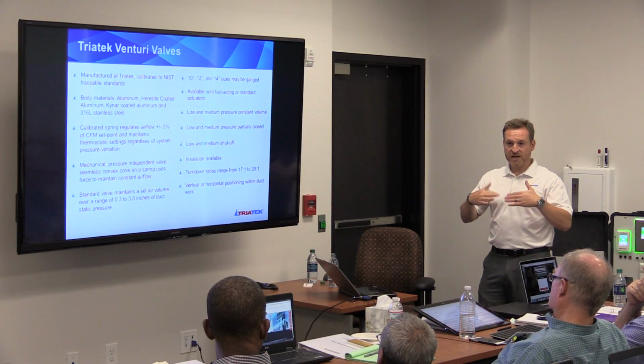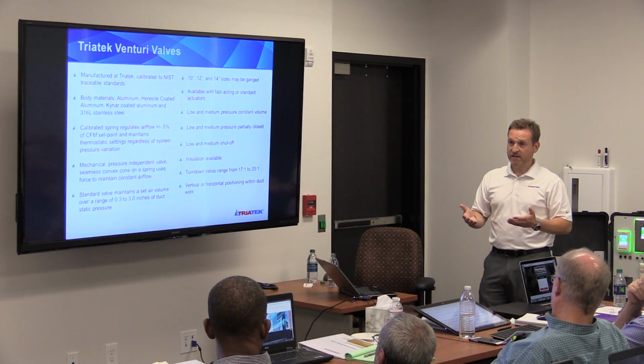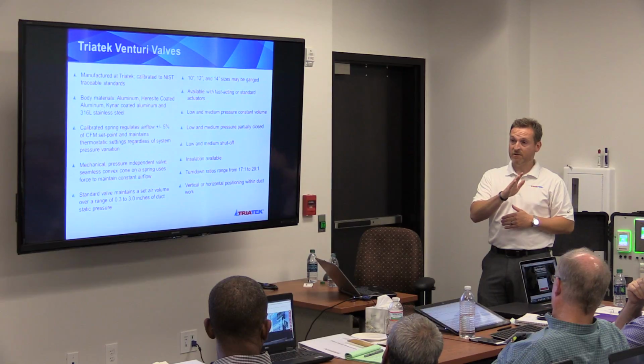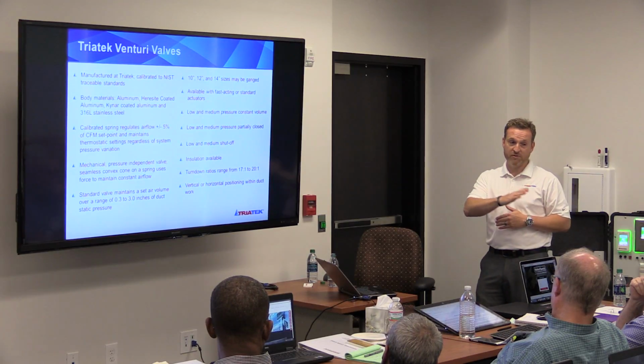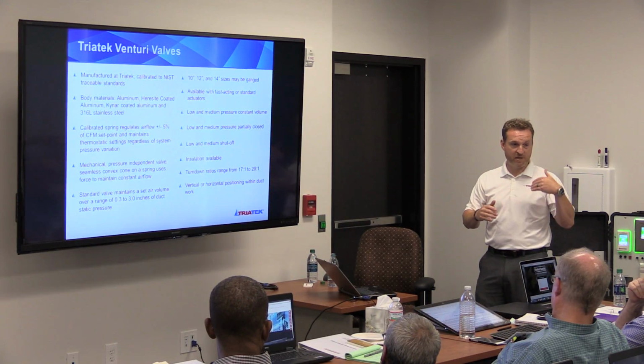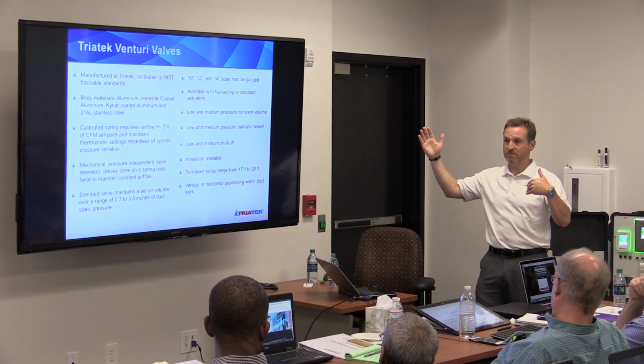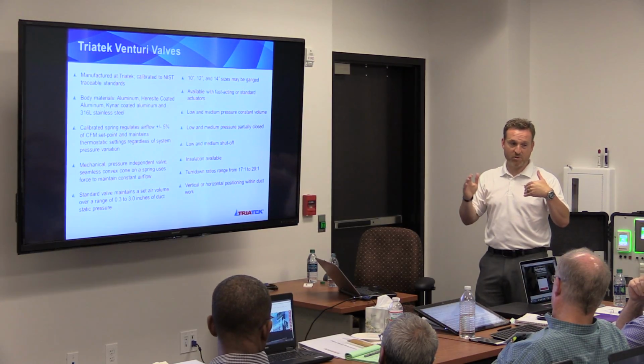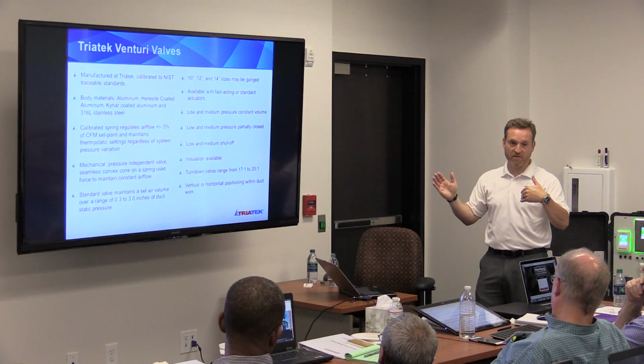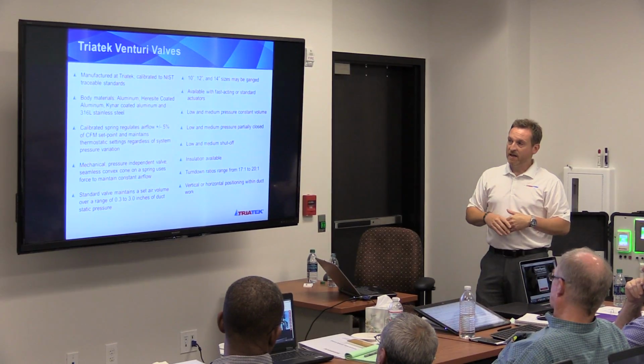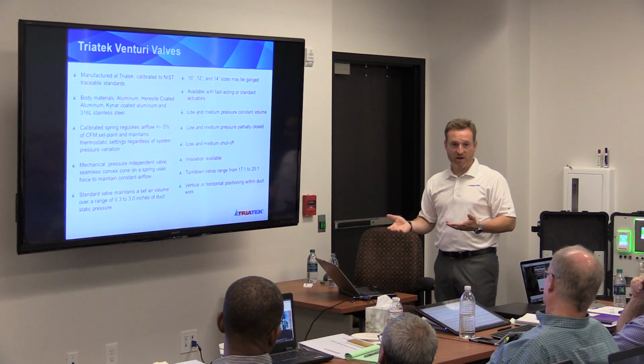With these valves, they're a calibrated device, and their accuracy is plus or minus 5% in the full range. So we could be at 50 CFM to 1,000 CFM, and we're going to maintain an accuracy of plus or minus 5% at all times in the range. Okay. Now these valves are also maintenance-free products.